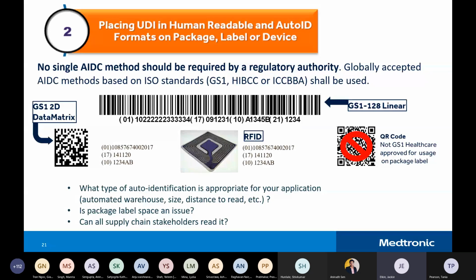In the US, they'll let you use what's referred to as a cross-reference method. If you can cross-reference the identifier that is on, say, your orthopedic screw, I know it's really tiny, with the UDI that belongs to that screw and make that available to the end user, that's acceptable in the US. Some manufacturers have developed tags that clip on to the head of the screw. But what I've seen mostly is manufacturers developing web portals where they do the cross-reference, using the identifier on the device. I know of a couple manufacturers that were doing it manually with paper about 4 years ago. I don't know if they're still doing that.